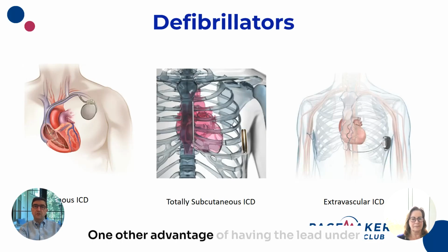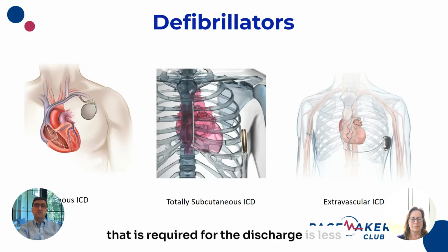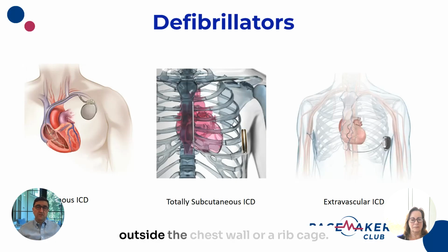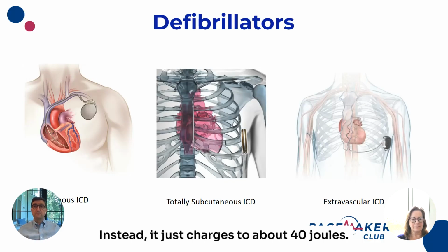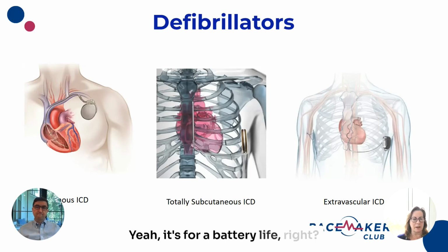One other advantage of having the lead under the breastbone is that the amount of energy required for the discharge is less because it's inside the chest wall, not outside the chest wall or the rib cage. And that means the generator can potentially last longer because it doesn't have to discharge to 80 joules. Instead, it just discharges to about 40 joules. So those are some of the key differences. Yeah, it's for battery life, right? Very important for the battery life.